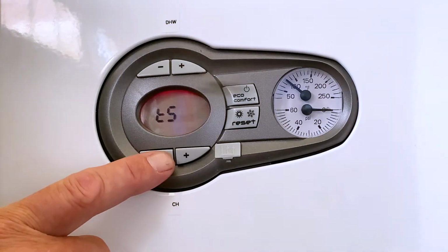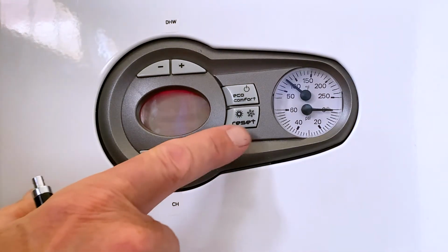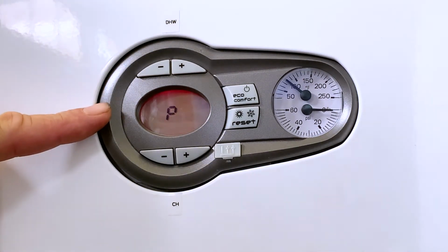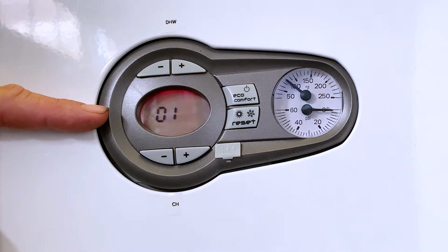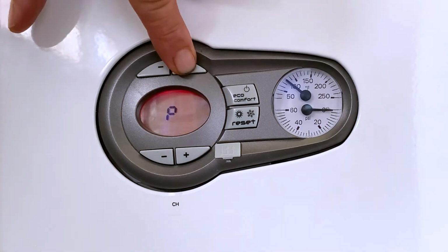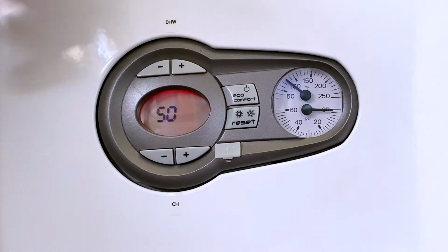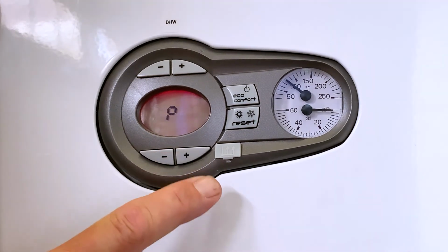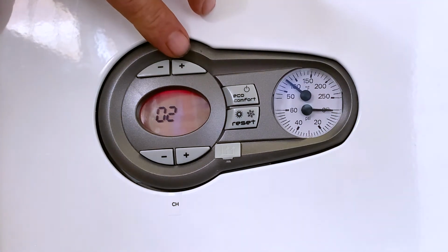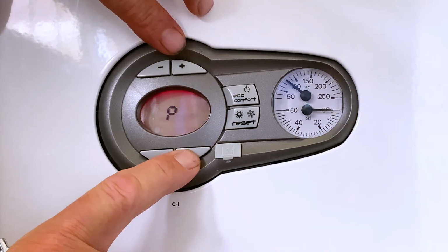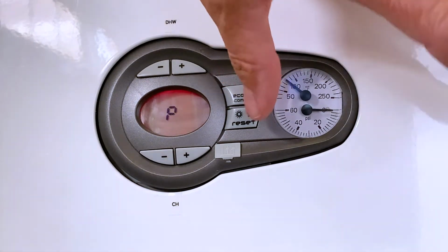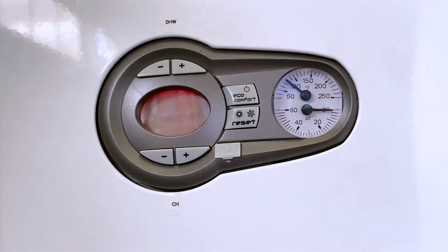At this point we now have the option to pick the menu that we want to go into. If I wanted to go into those transparency parameters, I would just push that reset button real quick, and it's going to show P01. The transparency parameters start with the letter P, as in playground, and then if I wanted to read the value of that, I just come up here and it's 50. Now if I want to look at the next one, we're going to go to the central heating set point down here, P02, read the value. I want to go to P03, P04, and so forth. You see how we're going there. Remember, to get in there, we pushed that reset button real quick. I'm just going to push the reset button again real quick.